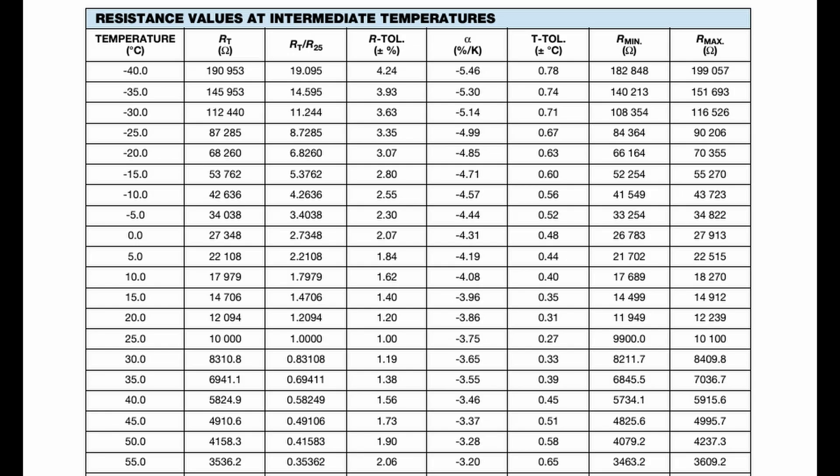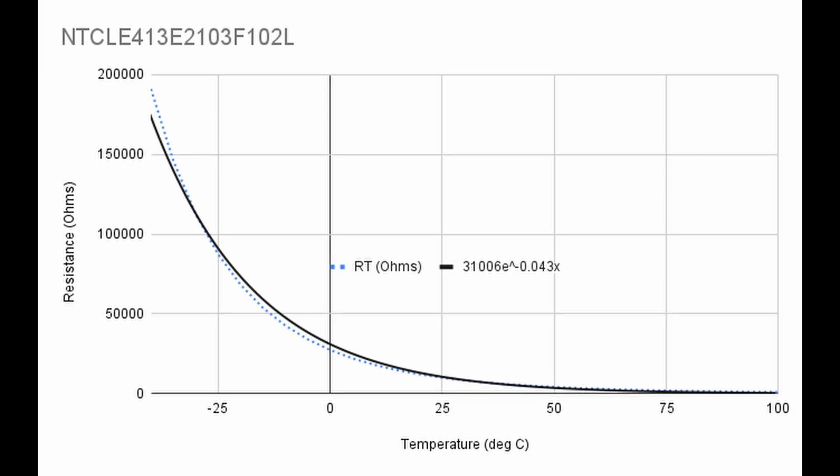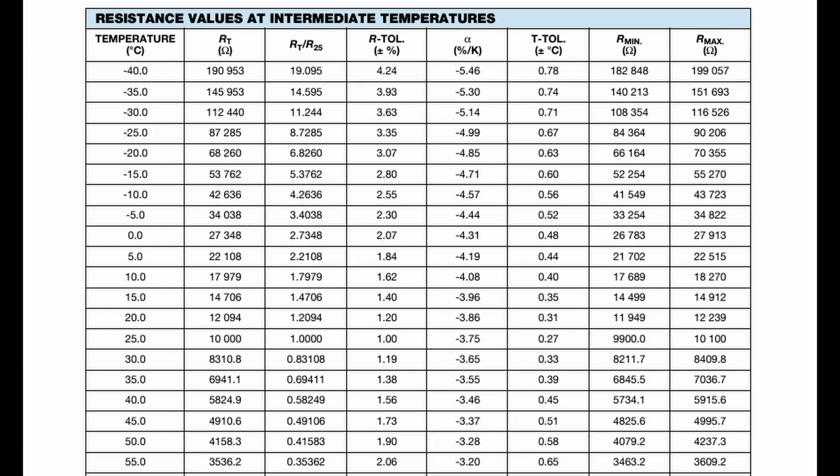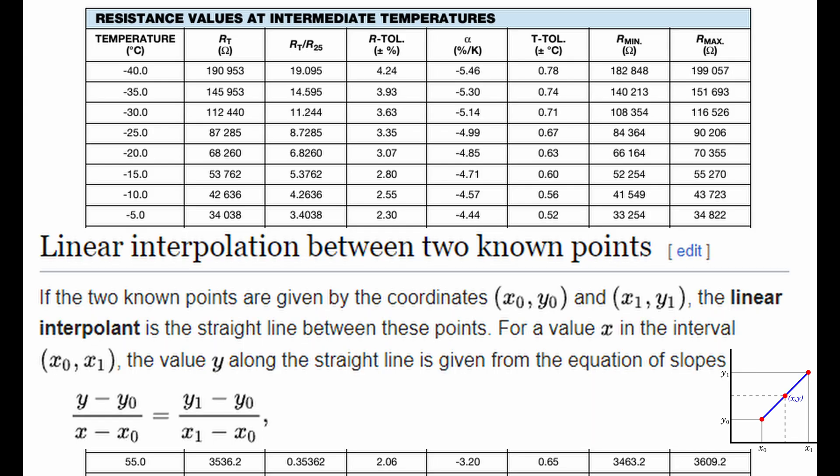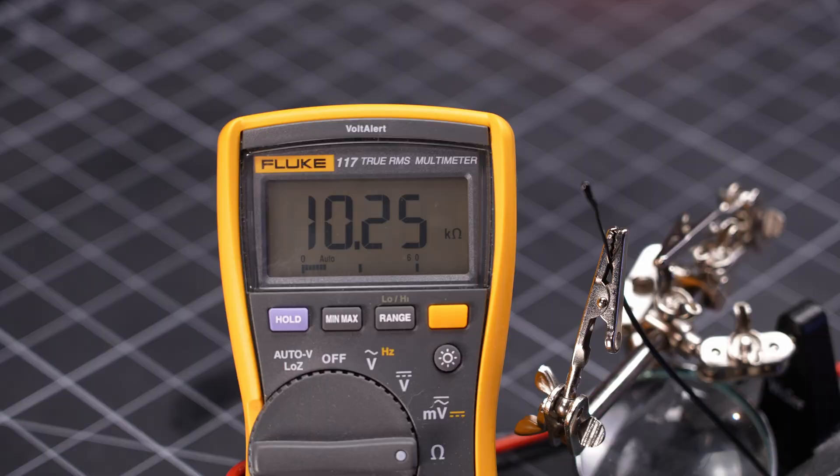But I instead decided to go with using a lookup table to try and minimize the errors on that front. I could also go with a higher-order fit, but once it goes beyond first-order, I frequently prefer to just go with a lookup table and interpolate. Just pop in the measured resistance and interpolate for the corresponding temp.